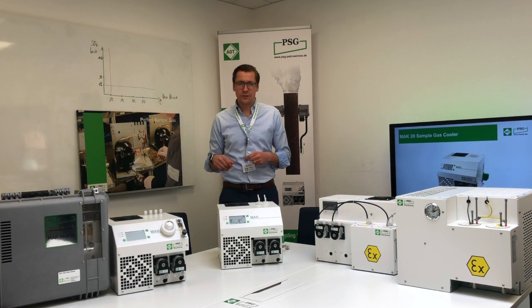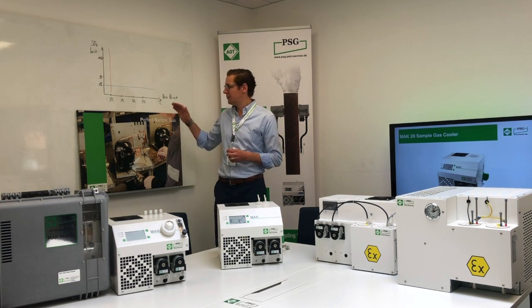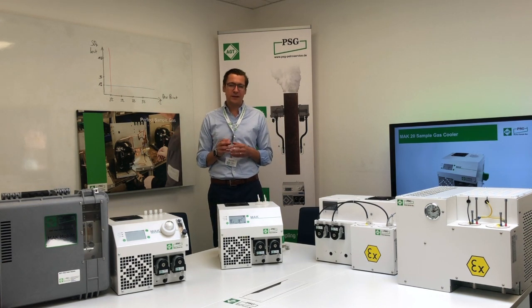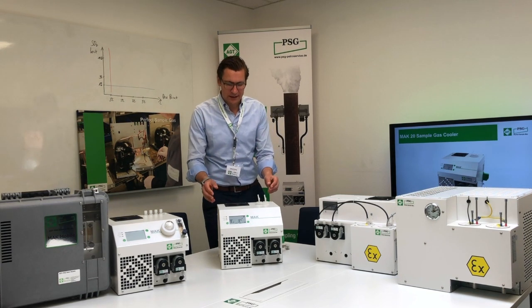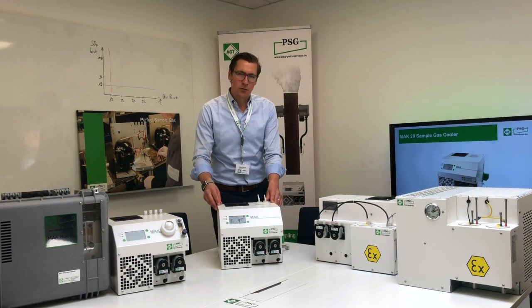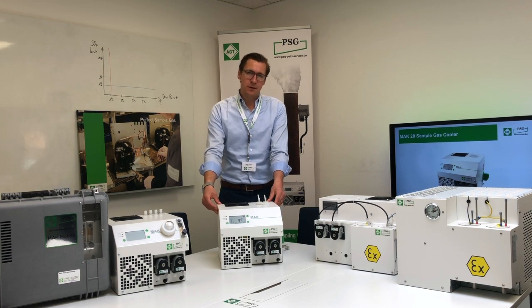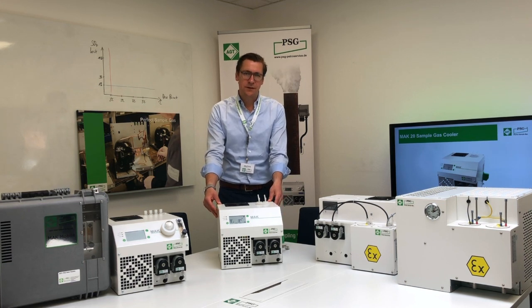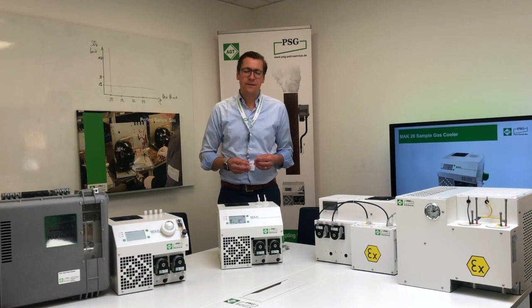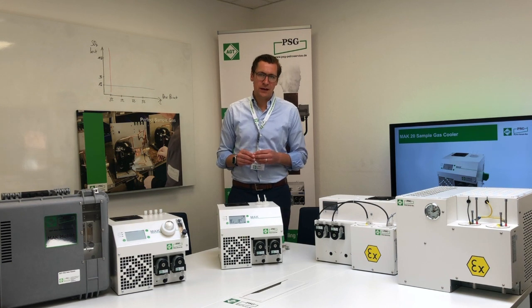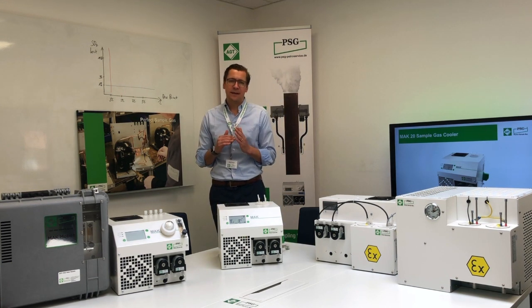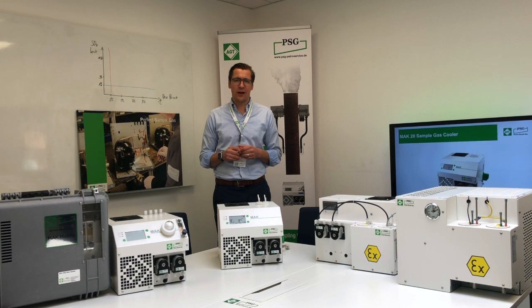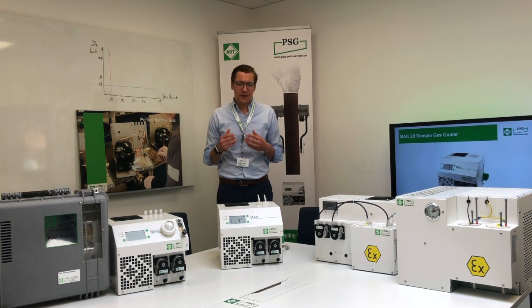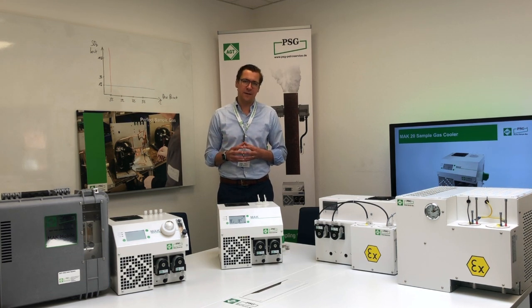If you remember the introduction, there are 2 criteria especially important for a product like this. The MAK series is mainly used for emission monitoring applications, which means there has to be a very good compromise between the SO2 washout rate on one side and the outlet dew point on the other. This describes the performance of a sample gas cooler.